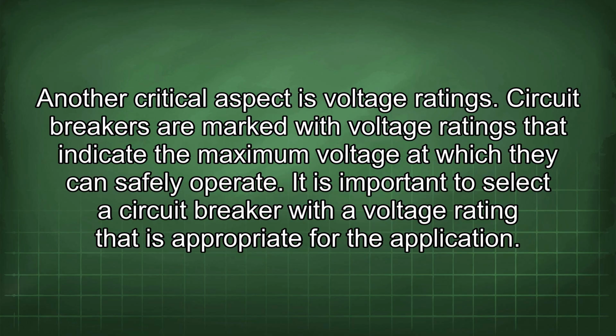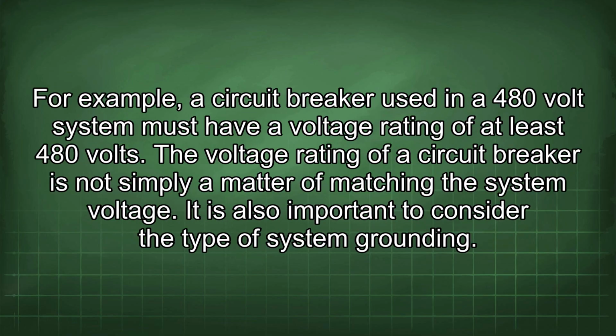Another critical aspect is voltage ratings. Circuit breakers are marked with voltage ratings that indicate the maximum voltage at which they can safely operate. It is important to select a circuit breaker with a voltage rating that is appropriate for the application. For example, a circuit breaker used in a 480-volt system must have a voltage rating of at least 480 volts. The voltage rating of a circuit breaker is not simply a matter of matching the system voltage. It is also important to consider the type of system grounding.